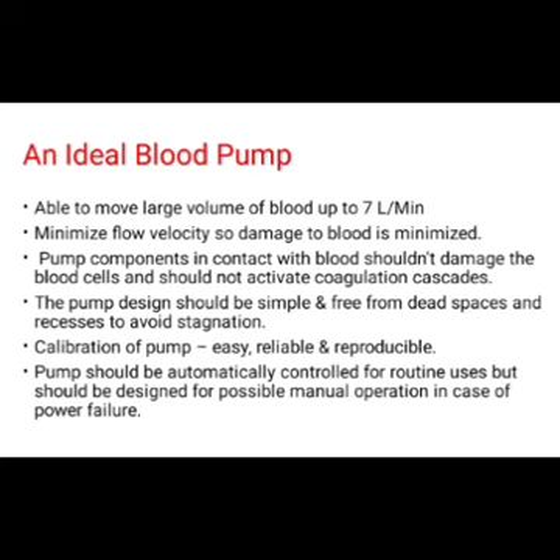What should an ideal blood pump have? It should be able to move a large volume of blood, up to 7 liters per minute. It also should minimize the flow velocity so the blood damage will be minimized. The pump components in contact with blood shouldn't damage the blood cells and should not activate coagulation cascades.